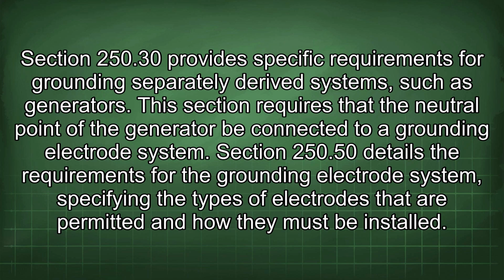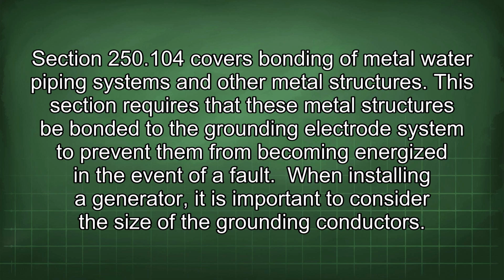Section 250.30 provides specific requirements for grounding separately derived systems, such as generators. This section requires that the neutral point of the generator be connected to a grounding electrode system. Section 250.50 details the requirements for the grounding electrode system, specifying the types of electrodes that are permitted and how they must be installed. Section 250.104 covers bonding of metal water piping systems and other metal structures. This section requires that these metal structures be bonded to the grounding electrode system to prevent them from becoming energized in the event of a fault.